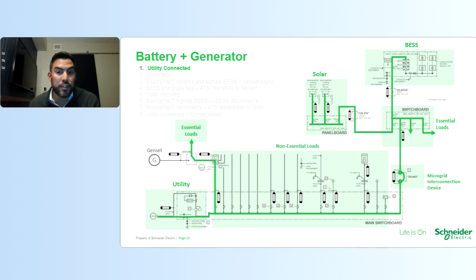This is the ideal configuration for a microgrid interconnection device, because here those essential loads are already separated in that critical switchboard upstream of the microgrid interconnection device. So in the event of an outage, the energy storage system is not providing power to those non-essential loads in your main switchboard. It's only providing power to those essential loads in that critical switchboard. So we'll go through this animation, and you can see how each of the ATSs operate, and how these inverter systems come online and shut down.